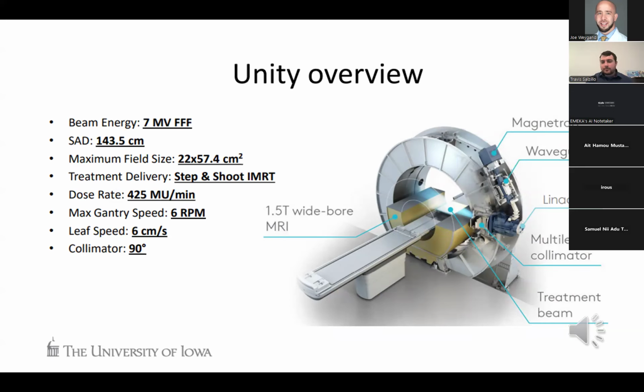one that I'm a little more familiar with, you'll see a very similar linear accelerator design. This is never a cobalt system. It had always started with a linear accelerator. But again, you have a magnetron for your power amplification, MLCs, and that rotates around the bore of the magnet. So some technical things about this. It's one energy, 7 MV, and it's a flattening filter free beam. So you can achieve fairly high dose rates, but it is a non-flattened beam profile.